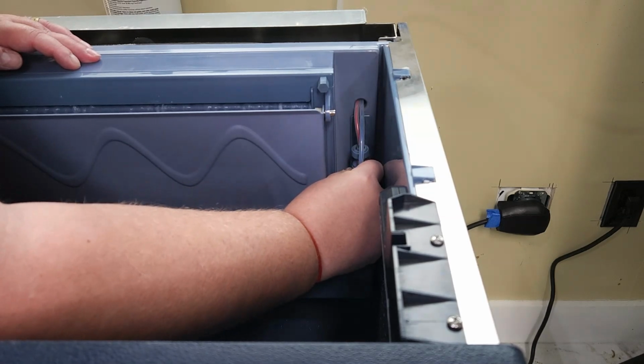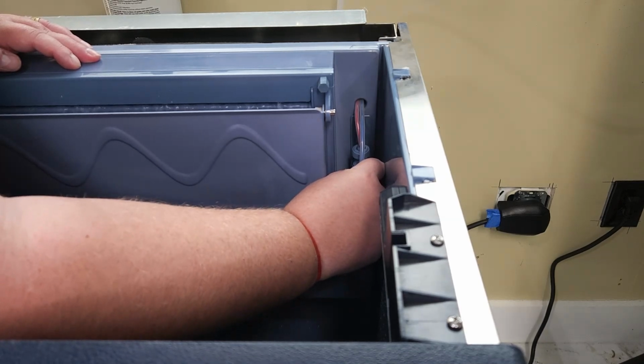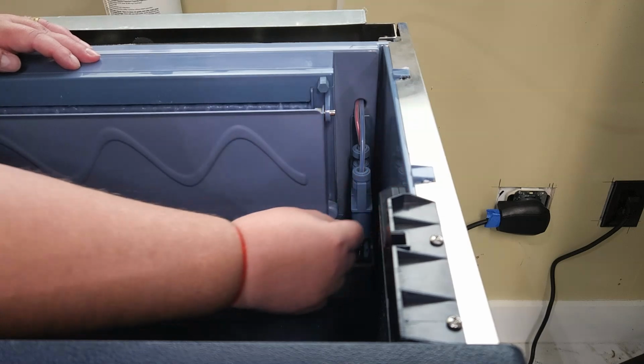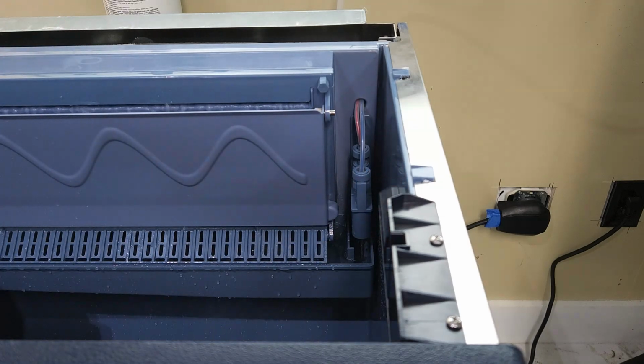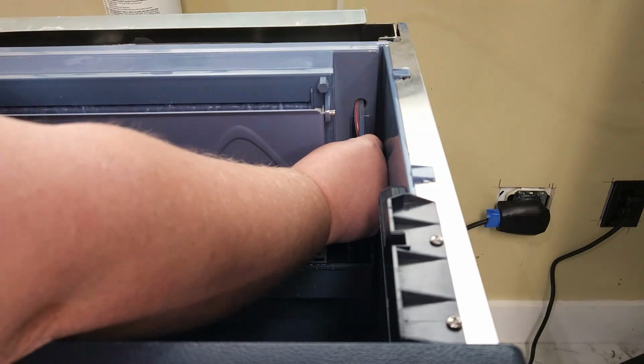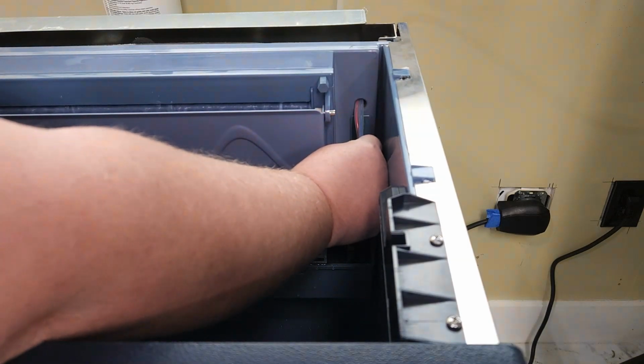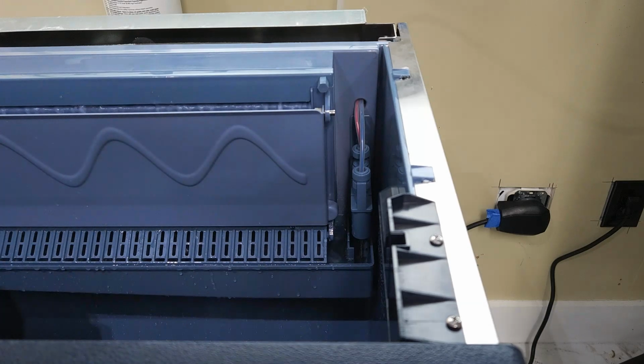To adjust the probe, begin by loosening the top plastic nut on the probe. Then you can turn the lower plastic nut on the probe to either raise or lower it. Clockwise will raise the probe and counterclockwise will lower the probe. In this case, we need to raise the probe. When you are done adjusting, remember to retighten the top nut so that the probe stays in place.